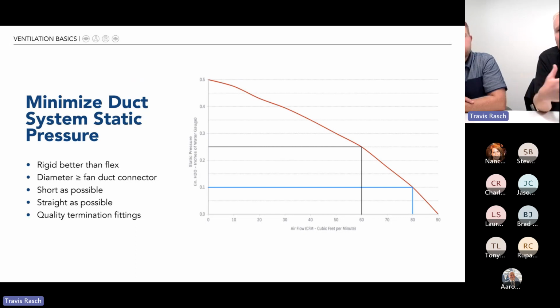Of course, with the ERV, it gets a little more complicated. There you have 4 ducts and you kind of have to look at the combined static pressure of the system. But the point here is, make sure HVAC contractors are really paying attention to this. You look at the bullets on the left: one, rigid ducting is better than flex. We don't want to minimize the duct diameter coming off the duct connector of the fan. If anything, increase it. Keep your duct run as short and straight as possible, and really think about quality termination fittings. You want them to be airflow friendly.